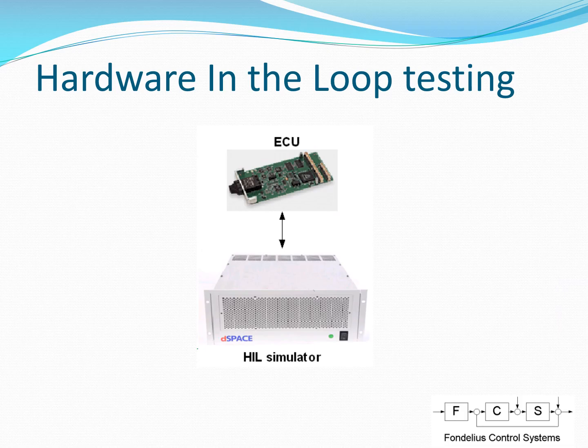In hardware in the loop testing we use the low voltage, low current interface to the converter control system and replace the environment surrounding it with the HIL simulator. Using tools such as Simulink we then design models representing the surrounding environment.